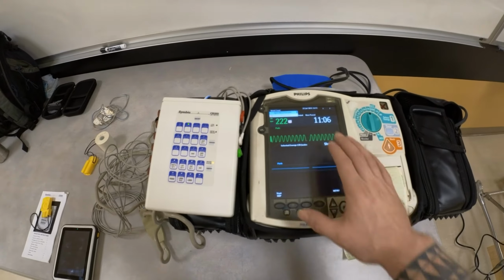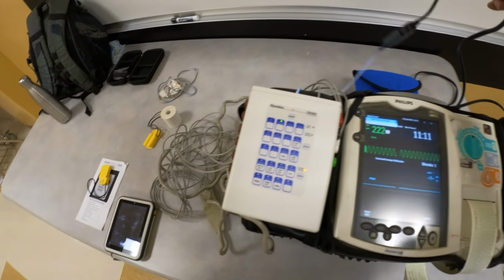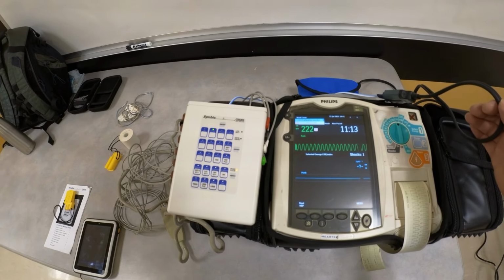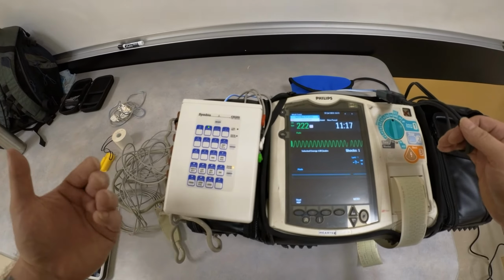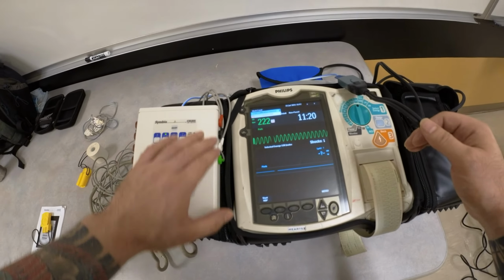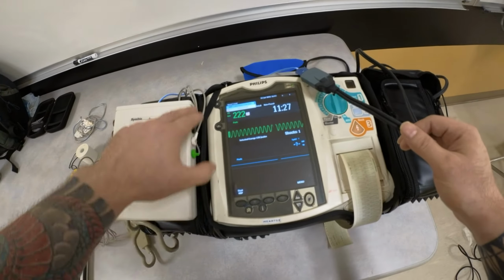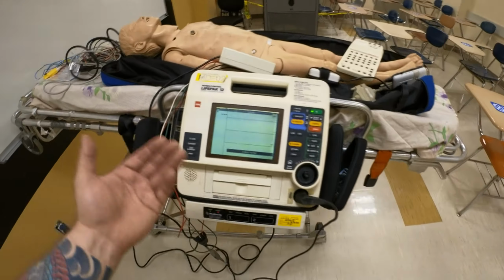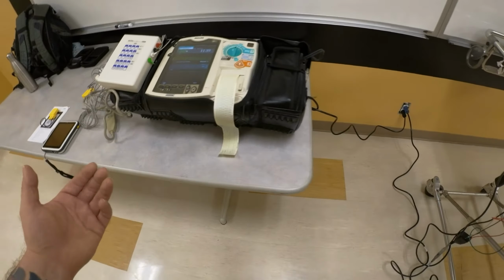And the problem with this is these monitors cannot both sense and provide electrical therapy through paddles alone. So what they will often say is your equipment is faulty or it's malfunctioning. And the answer to that is not. It's that you need to apply both the limb leads and the ECG pads in order to provide electrical therapy, because this cannot sense and provide electrical therapy through this alone. So you need these devices to read the rhythm and provide electrical therapy. Now, if you're using a mannequin like this one, you could explain this to the students and see them apply these leads appropriately. On this device, you are unable to do so.